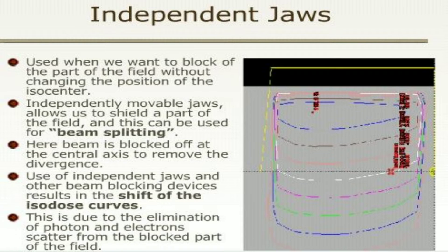Independent jaws are used when we want to block off part of the field without changing the position of the isocenter. Independently movable jaws allow us to shield a part of the field and can be used for beam splitting. The beam is blocked off at the central axis to remove the divergence. Use of independent jaws and other beam blocking devices results in a shift of isodose curves, due to the elimination of photon and electron scatter from the blocked part of the field.